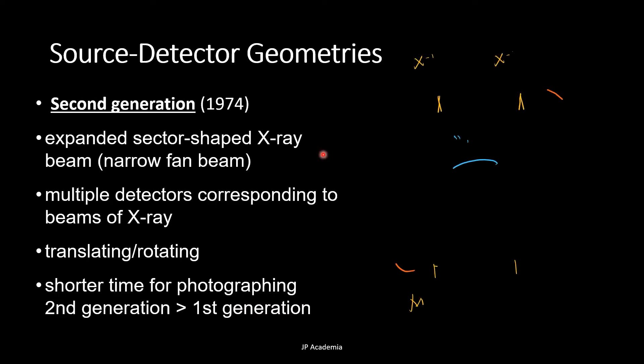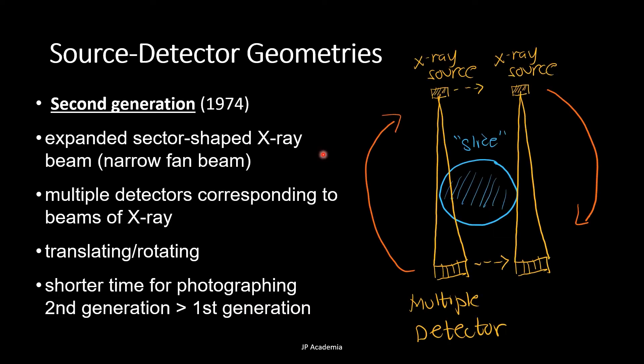Next, we have the second generation. It has an expanded sector shape of X-ray beam, described as a narrow fan beam, as shown here. It has multiple detectors corresponding to beams of X-rays, and its motion is described by this. So it will translate first as it scans the patient, then it will rotate to another angle. It has a shorter time for photographing compared to the first generation.